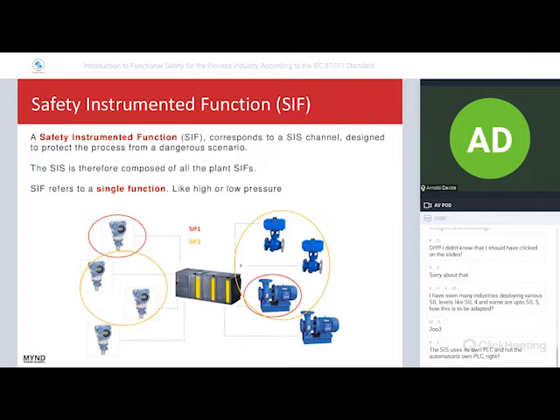While the safety instrumented system is only for safety. Then, inside the safety instrumented system, as I told you before, it is the collection of all safety loops. These safety loops are normally called safety instrumented functions, which correspond to a SIS channel designed to protect the process from a dangerous scenario. A dangerous scenario is, for example, high pressure, high level, or low level. One step after the dangerous scenario is the dangerous event, for example, explosion of the tank due to high pressure.